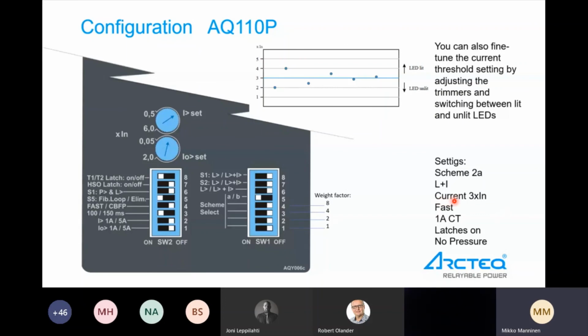From the design, we can find that the current threshold for this design is 3 times nominal. We can turn this potentiometer to 3. First, we can select that we have a 1 amp CT. We can inject a constant 3 amps with Omicron or any other test kit. And then turn these potentiometers left and right and try to find the threshold level, under, over, under, over, and fine tune it to the closest to 3 times nominal.